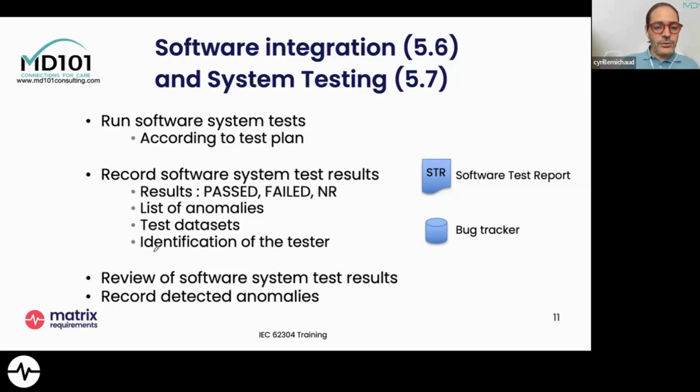And we need also to review these test results to be sure that what has been recorded in the test results is, first, aligned with the content of the test plan, of course, and also compliant to the standard requirements.